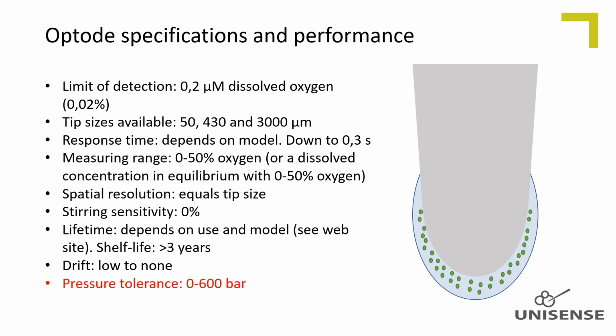Oxygen optodes stand up to 600 times atmospheric pressure when connected to our deep-sea optode meter. We cannot, however, guarantee that the calibrations done at 1 bar give accurate measurements at pressurized conditions. The polystyrene/dye matrix might change properties which have not been validated in detail.